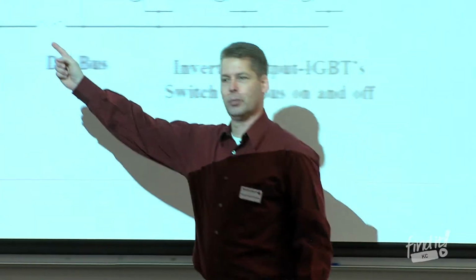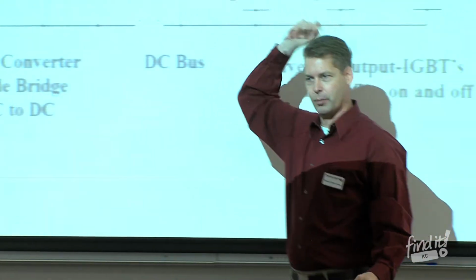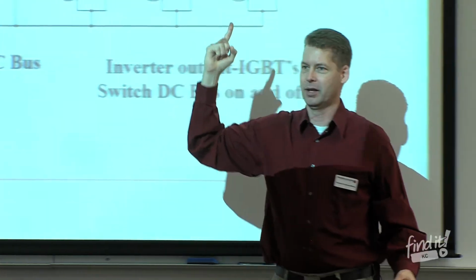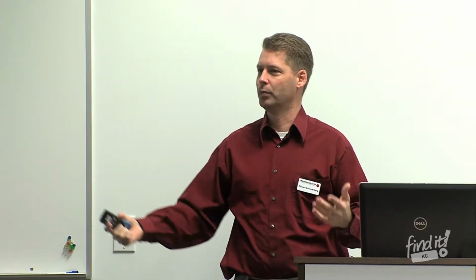Why do we go to all the trouble to take AC, turn it to DC, just to turn it back to AC? Anybody got an idea? So we can slow it down, because there's no way to actually change the frequency of power coming from the utility company, but we can change the frequency by using these transistors here, and by changing the frequency we send to the motor, we slow the speed down.